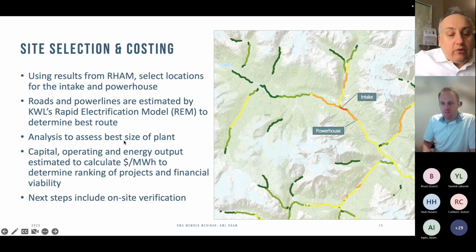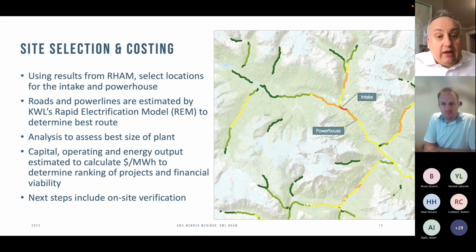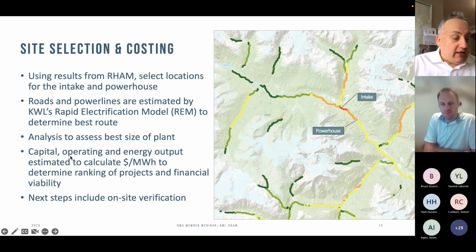In the case of this work we're doing for Natural Resources Canada, we're looking at the loads of these small communities and mines over the year and sizing the plants so that if there's enough power potential at the location near the community, it can meet the peak electricity demand in the winter, so that there's the opportunity to completely displace the diesel generation. Probably leave the diesel plants there for backup, but try and minimize the amount of diesel use.